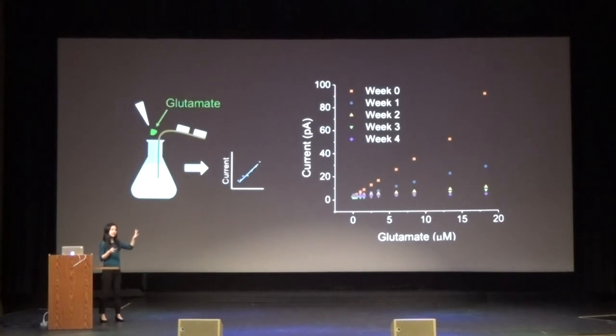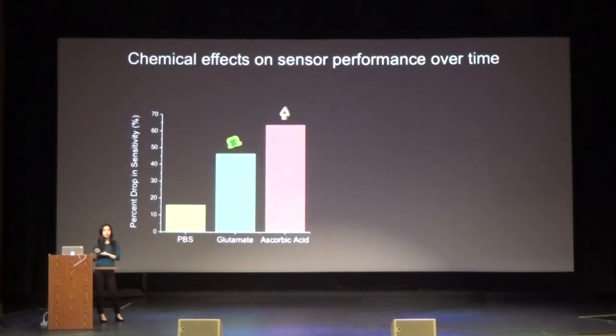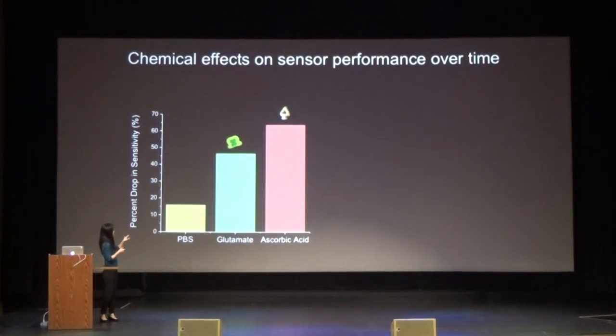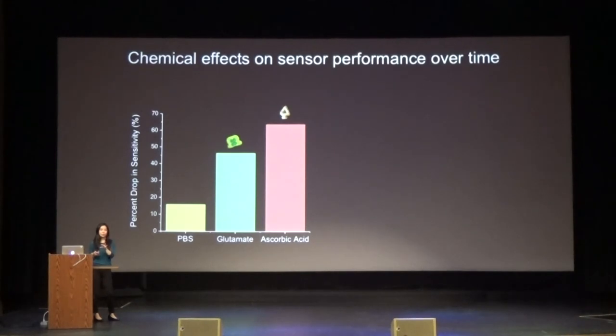I did these same tests for all three soak solutions shown before, so here's a comparison of the device soaking in PBS, glutamate, and ascorbic acid, with the y-axis showing percent drop in sensitivity the longer it soaks. I want to emphasize it's a percent drop, so the bigger the bar in this graph, the worse the device performed. The device soaking in PBS showed about a 15% drop in sensitivity, but the devices soaking in glutamate or ascorbic acid showed at least a 50% decrease in sensitivity over the same time period.